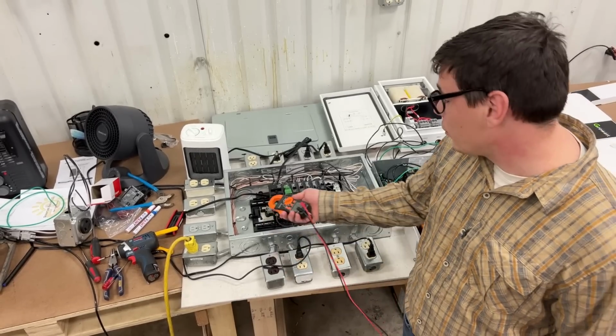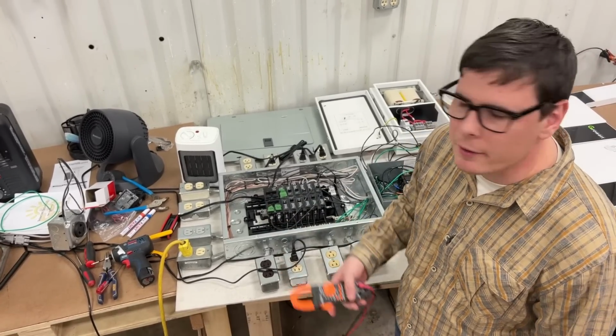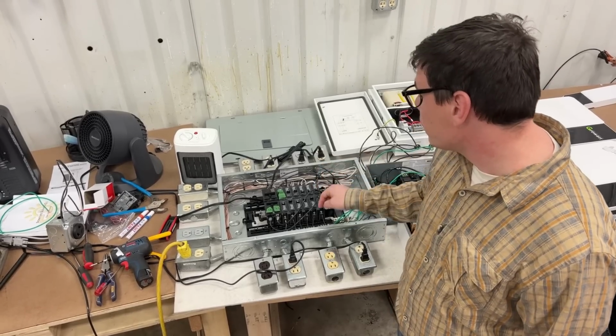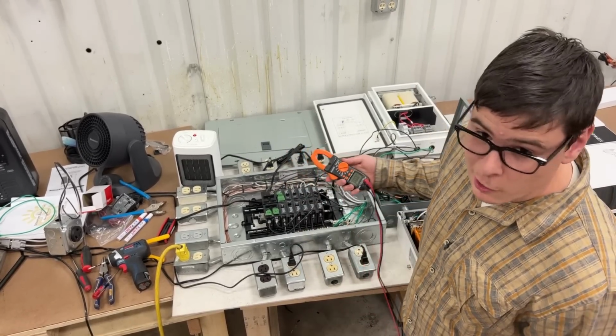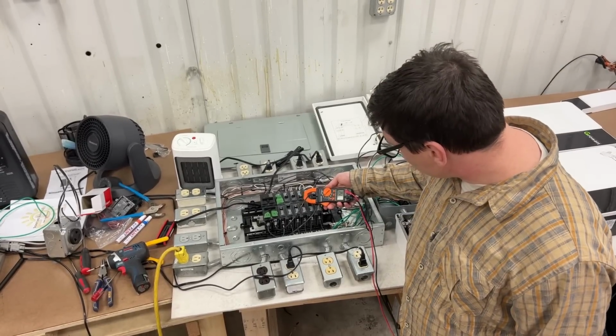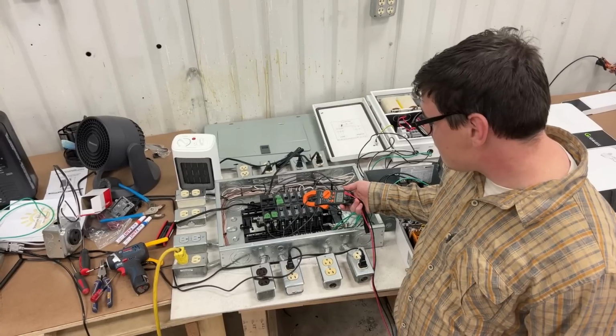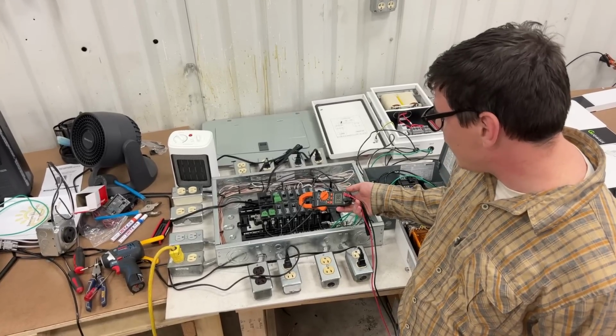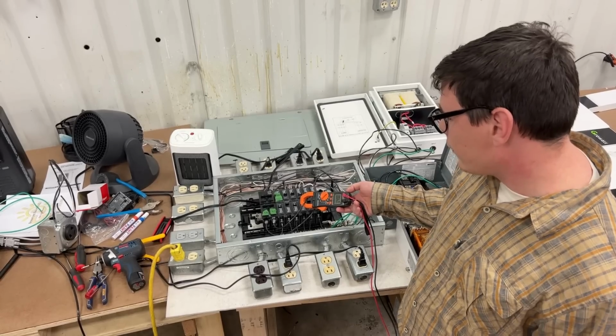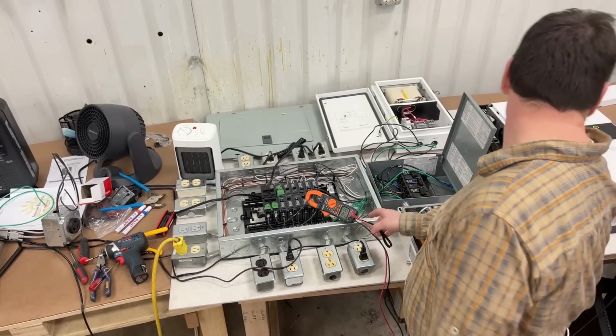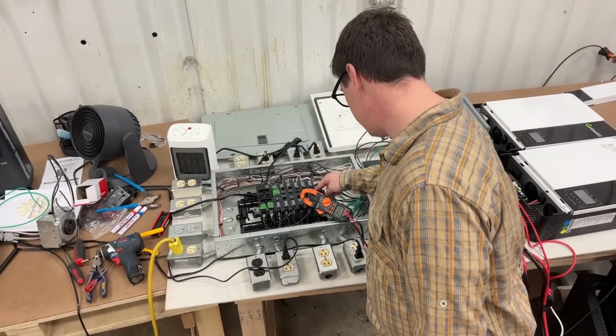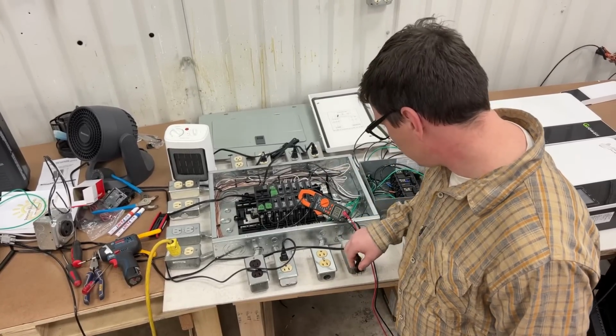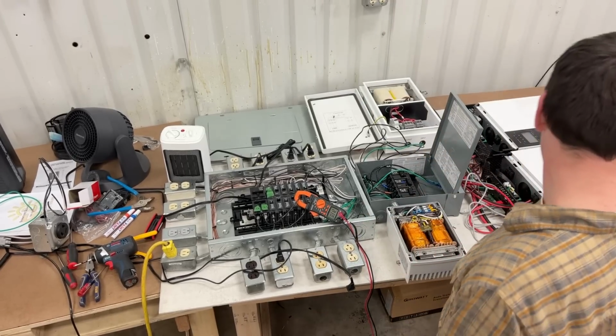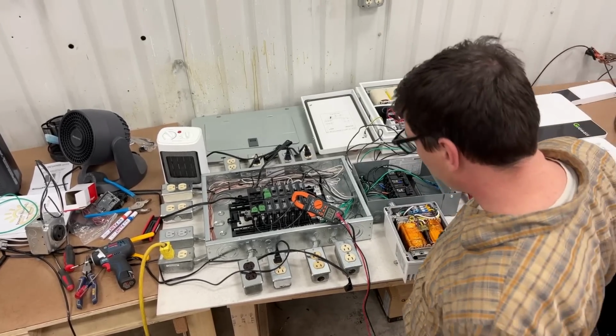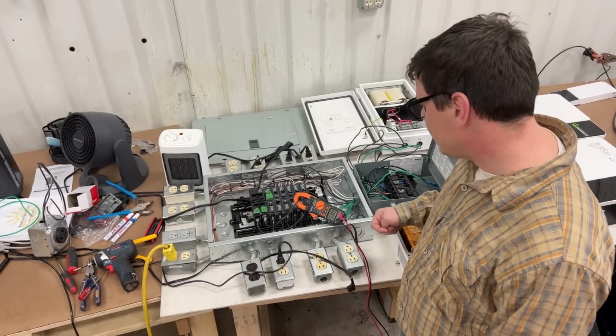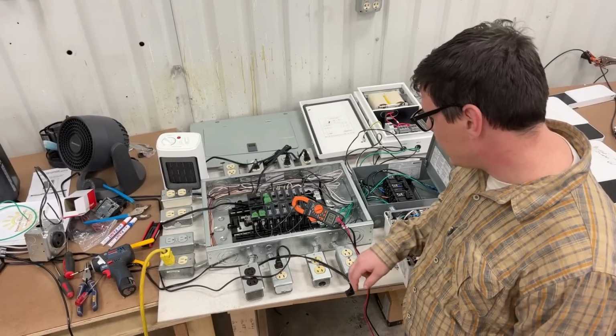Now 28 amps eventually is going to trip this 25, but it's going to take a while and I don't have time for that. So let's go ahead and turn on another heater, because we're that psycho, and we're at 35 amps. 37 amps, 38 amps. And it can't be too long, guys. This will trip. Oh shoot, this inverter doesn't like that. We're at 31 amps. So it's getting above one inverter's capacity. 30 amps. Hey, come on.